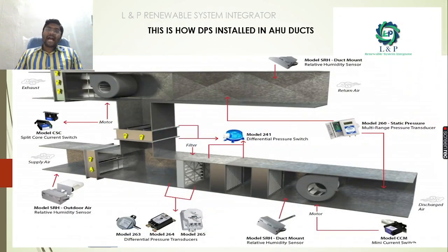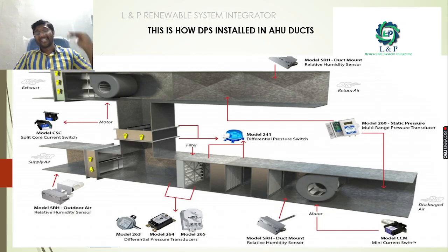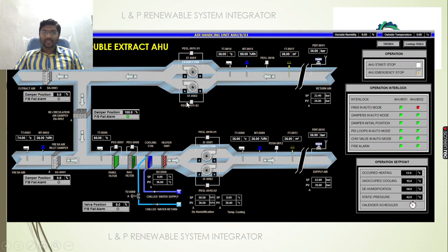In an air handling unit, differential pressure switches are installed across the supply side, return side, exhaust side, and recirculation side. The AHU has two filters — differential pressure switches are installed across these filters. If required, switches can also be installed across fans. Based on the application and pressure set point range, we choose the appropriate differential pressure switches. The schematic shows panel filter and bag filter installations with differential pressure switches in healthy ranges, along with fan flow monitoring on both supply and exhaust sides.